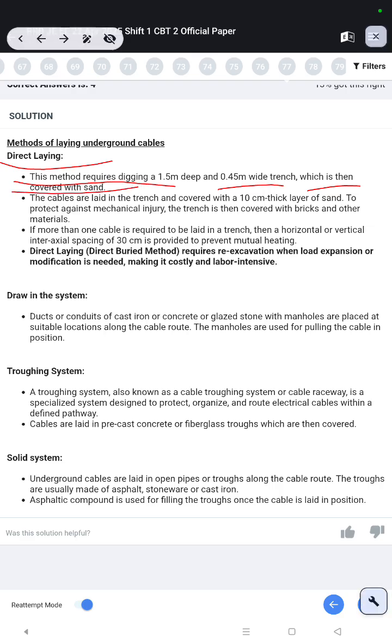The cables are laid in the trench and covered with a 10 cm thick layer of sand to protect against mechanical injury. The trench is then covered with bricks and other material. If more than one cable is required to be laid in a trench, then a horizontal or vertical interaxial spacing of 30 cm is provided to prevent mutual heating. Direct laying requires re-excavation when load expansion or modification is needed, making it costly and labor intensive.